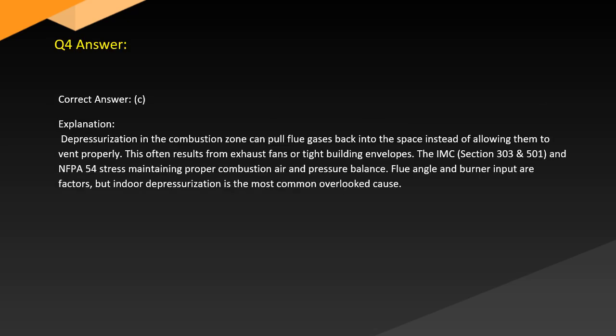Answer. Correct answer, C. Explanation. Depressurization in the combustion zone can pull flue gases back into the space instead of allowing them to vent properly. This often results from exhaust fans or tight building envelopes. The IMC Sections 303 and 501 and NFPA 54 stress maintaining proper combustion air and pressure balance. Flue angle and burner input are factors, but indoor depressurization is the most common overlooked cause.